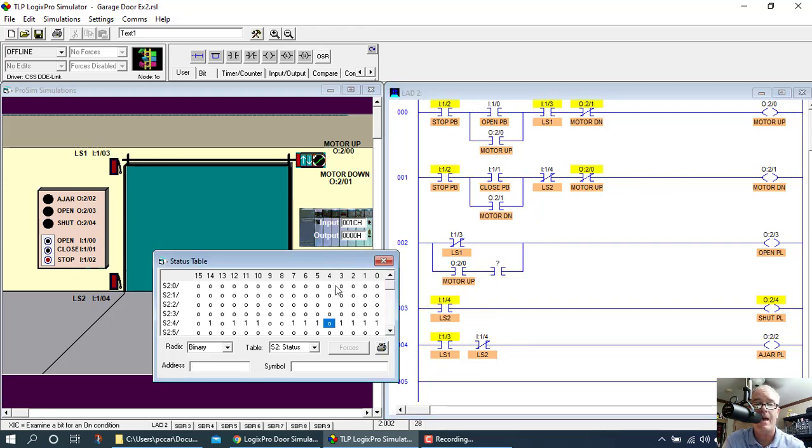And then we're going to give it the address of S2:4/4. You can type that in where the question mark is. Just double click on the question mark. You can type it, or you can just simply drag this bit over there and then make sure that it's correct. S2:4/4. The 2 was not used because it's understood and it's dropped. So it's just S:4/4. And that's completely fine. The program's not going to keep the 2 anyway, even if you type it.